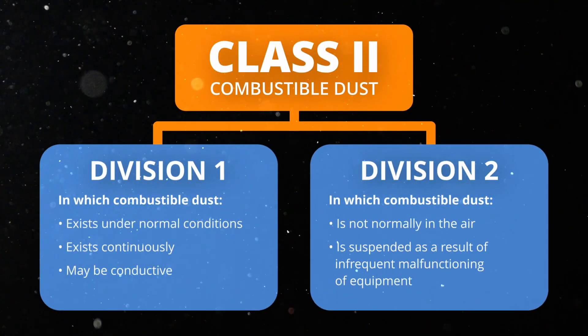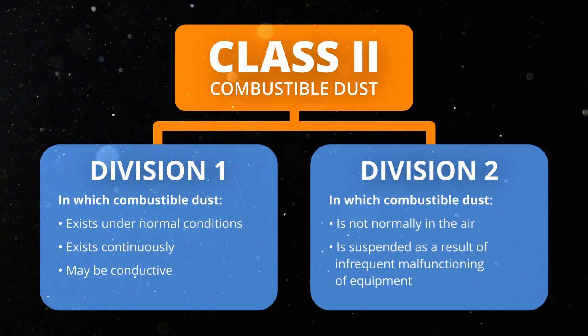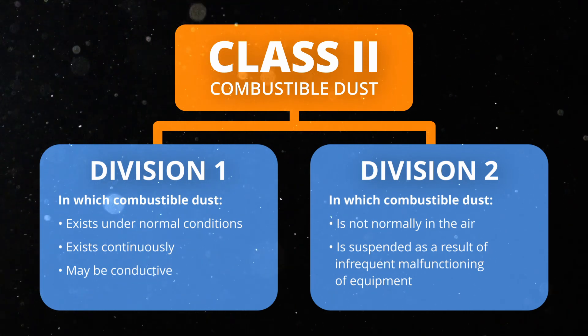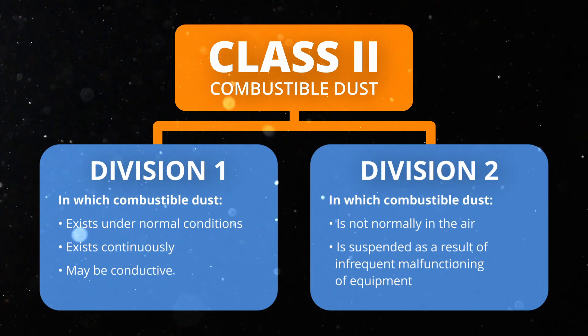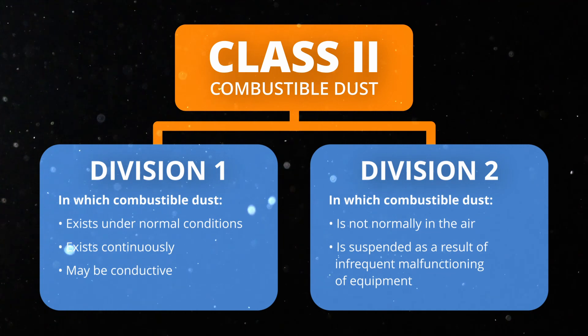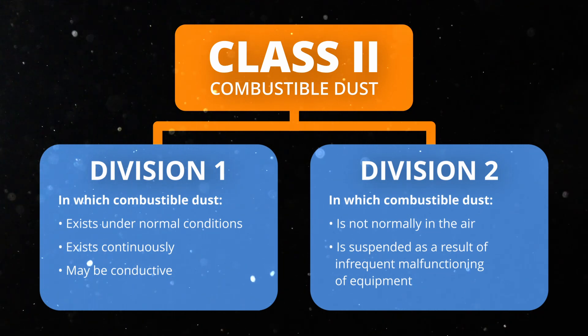Once you have determined that there are particular areas of handling or generating dust within your facility that should be considered class 2 rated, you must determine if they should be division 1 or division 2. Division 1 means that a combustible dust hazard exists regularly, whereas division 2 should be used for areas where the hazard exists infrequently — such as if a machine malfunctions or there's a clean-out process that occurs periodically.